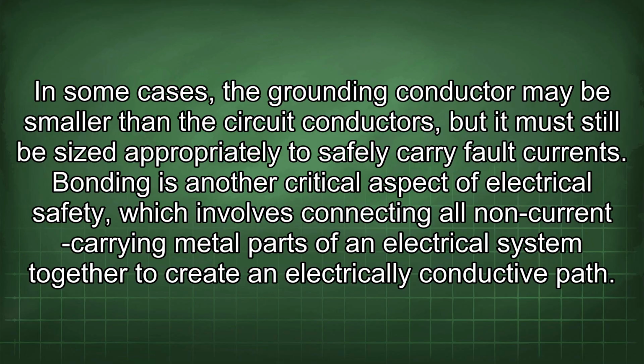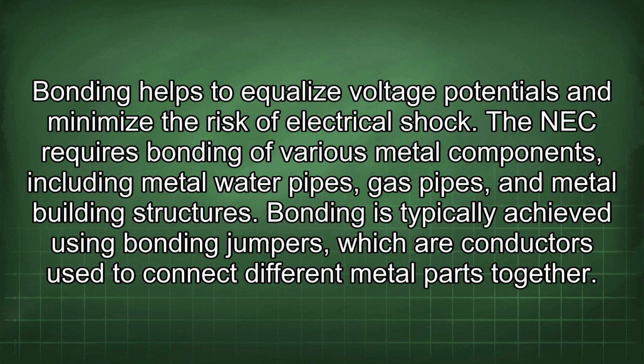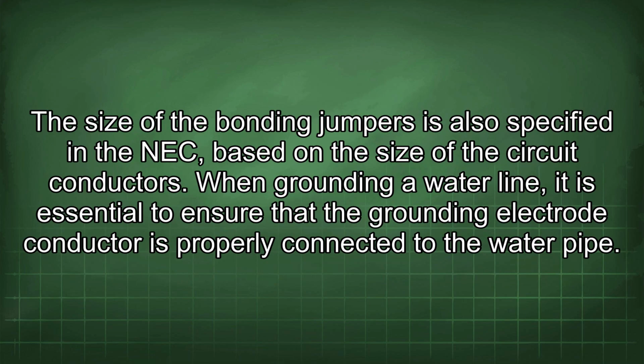Bonding is another critical aspect of electrical safety, which involves connecting all non-current carrying metal parts of an electrical system together to create an electrically conductive path. Bonding helps to equalize voltage potentials and minimize the risk of electrical shock. The NEC requires bonding of various metal components, including metal water pipes, gas pipes, and metal building structures. Bonding is typically achieved using bonding jumpers, which are conductors used to connect different metal parts together. The size of the bonding jumpers is also specified in the NEC, based on the size of the circuit conductors.